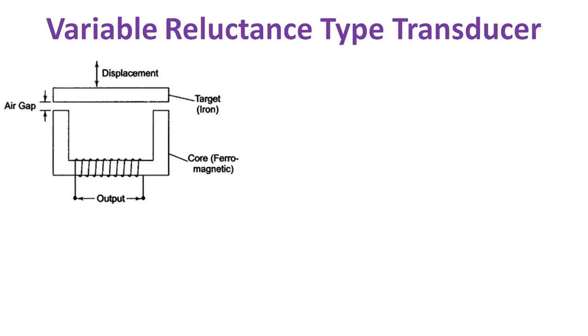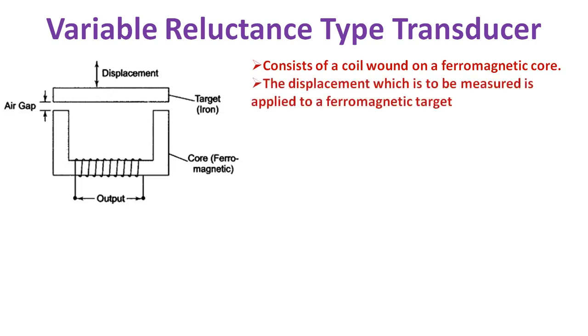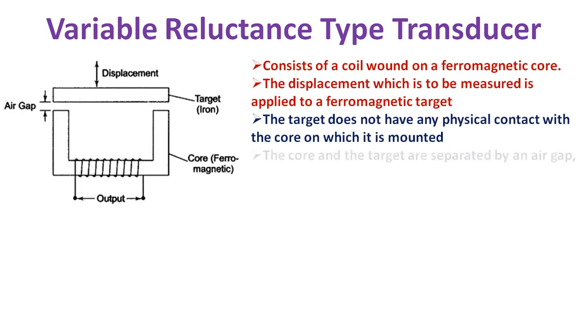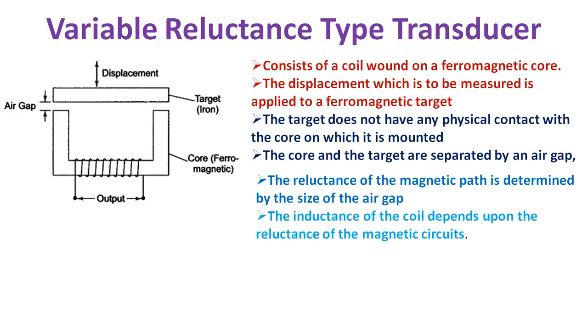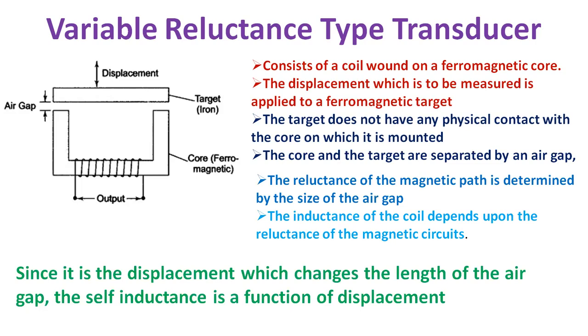Then we have the variable reluctance type of transducer. It consists of a coil wound on a ferromagnetic core. The displacement to be measured is applied to the ferromagnetic target, which has no physical contact with the core. The core and the target are separated by an air gap, as seen here. The reluctance of the magnetic path is determined by the size of the air gap, and the inductance of the coil depends on the reluctance of the magnetic circuit. When the target is near the core, the air gap is small and therefore the self-inductance is large. When the target is away from the core, the reluctance is large, resulting in a smaller self-inductance value. Hence, the inductance of the coil is a function of the distance of the target from the core — the length of the air gap — and since displacement changes the air gap length, the self-inductance is a function of displacement, albeit a non-linear one.